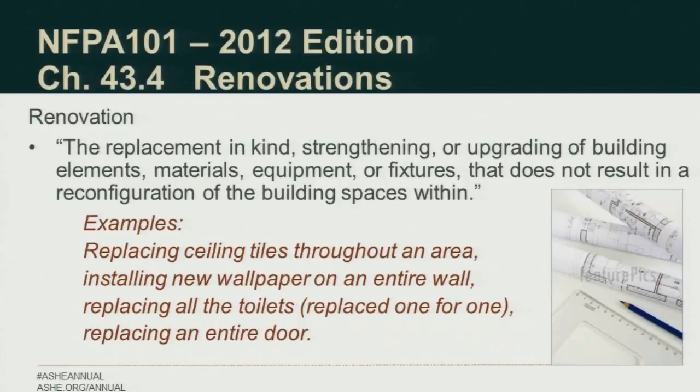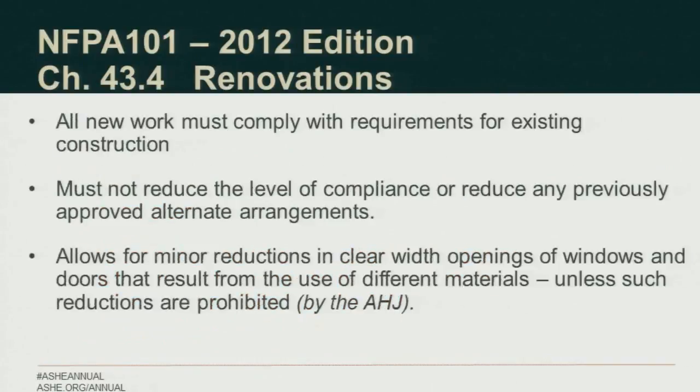A renovation takes it to the next level. All right, so here it's not just replacing or repairing something, but I'm replacing the ceiling tiles throughout this room, or I'm replacing the carpet throughout the room. I'm replacing a bunch of toilets in a bathroom, not just one for one. Here it says all new work must comply with requirements for existing construction. Not new, existing. Again, must not reduce the level of compliance to anything below what it was before.